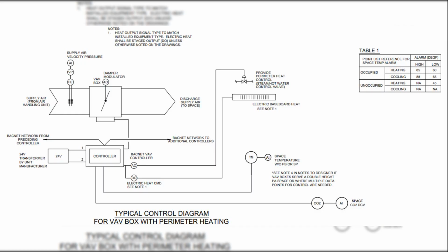Many VAV boxes in SCA projects also have a reheat coil, usually with hot water. When the classroom is too cool, that coil warms the supply air before it enters the space. This way, the system can both cool and heat the classroom as needed. The brains of the unit is the BACnet controller mounted on the outside of the box. This controller takes input from sensors, like the room temperature sensor, the carbon dioxide sensor for demand-controlled ventilation, and the velocity sensor that measures airflow. It constantly makes small adjustments to keep the classroom comfortable while saving energy. From the building management system, operators can monitor every VAV box. They can see alarms, adjust settings, and confirm that the box is delivering the right airflow and temperature.